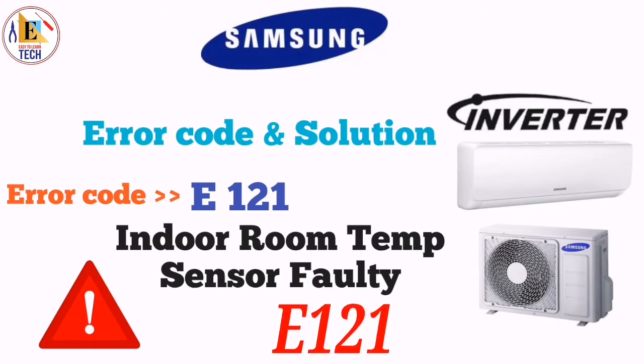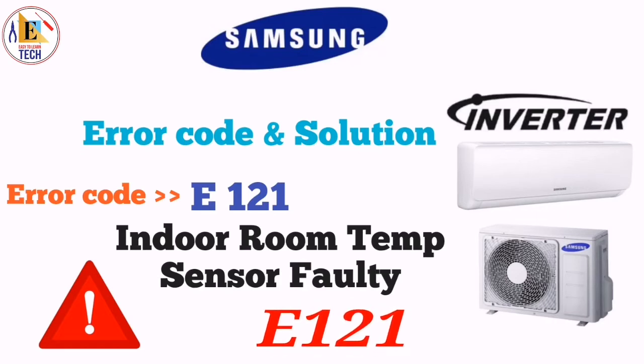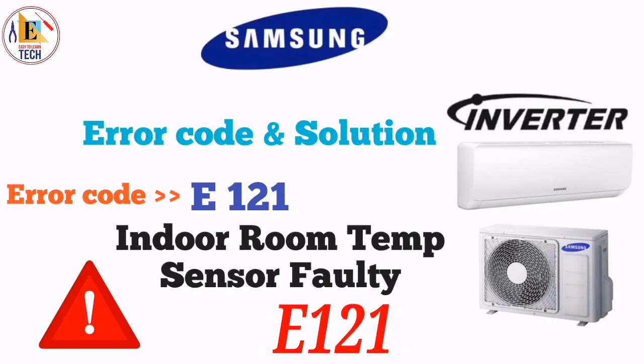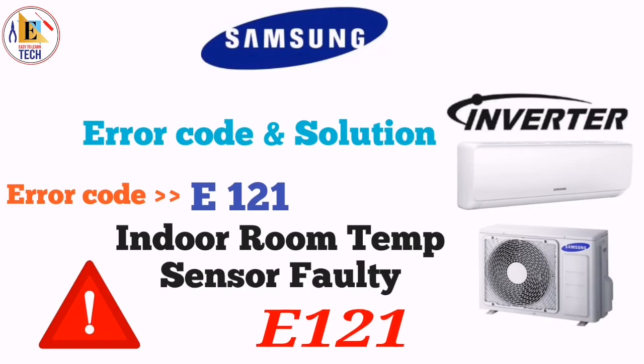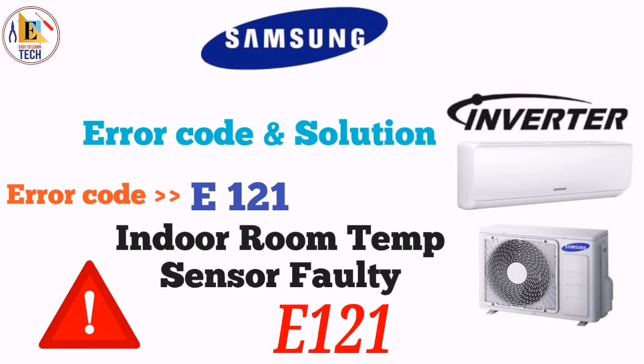And if both are good, then you have to check the resistance value according to the temperature. Detach the assembled sensor from the PCB sensor connector and measure the sensor resistance with an ohm meter or tester. The sensor resistance value should be 10 kilo ohm plus minus 3% at the room temperature of 25 degrees Celsius. If your resistance value is 10 kilo ohms, then go for the next step.